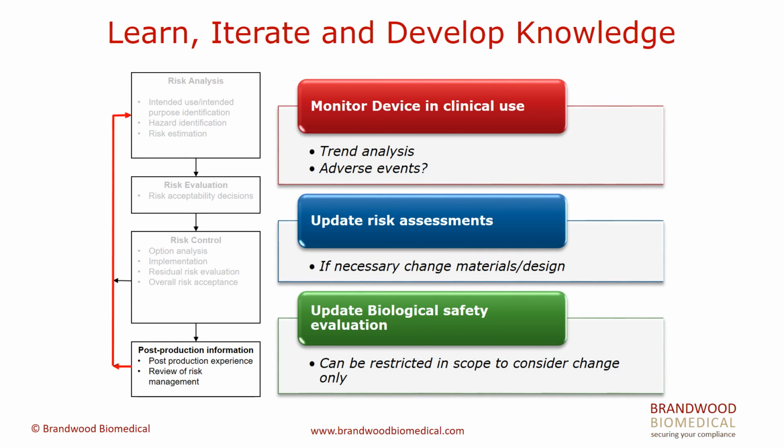And then the final step, of course, in risk management is that it's a living process, and you learn from post-production information, from placing the device in the field, in the clinic, and we learn. Monitor the device in clinical use, see what trend analyses we have. Are we seeing adverse events relating to biological safety? If necessary, we may need to update our risk assessments or change the device.